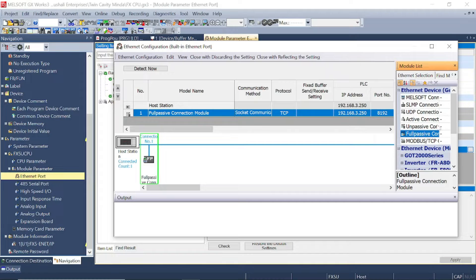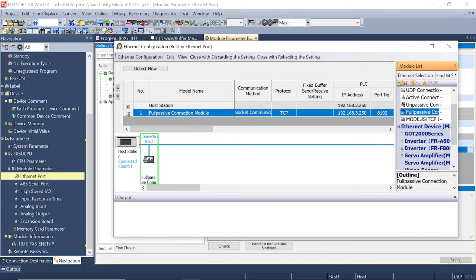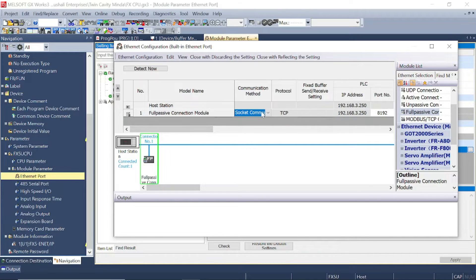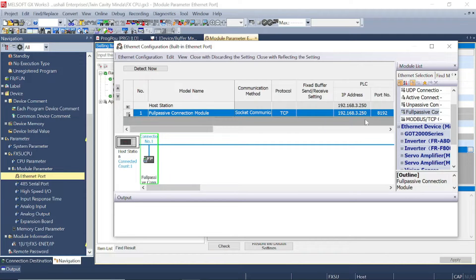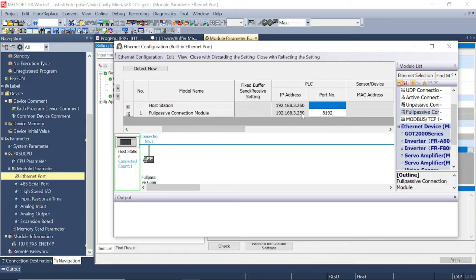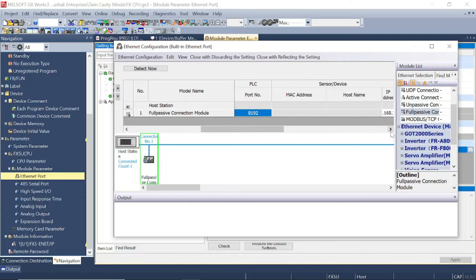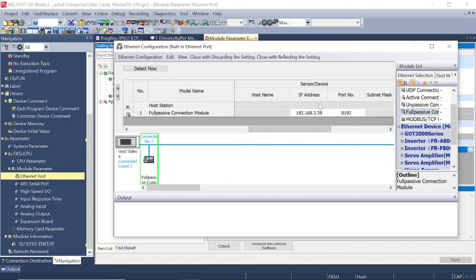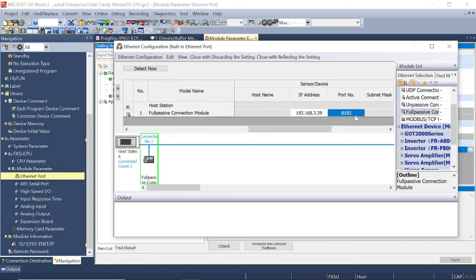This is the full passive connection — just drag this and drop it here. Then select the protocol: socket communication. This is the IP address of the host, and port number is 8192, which we recently entered in the Q series parameter. This is the Q series PLC IP address and the port number 8192.